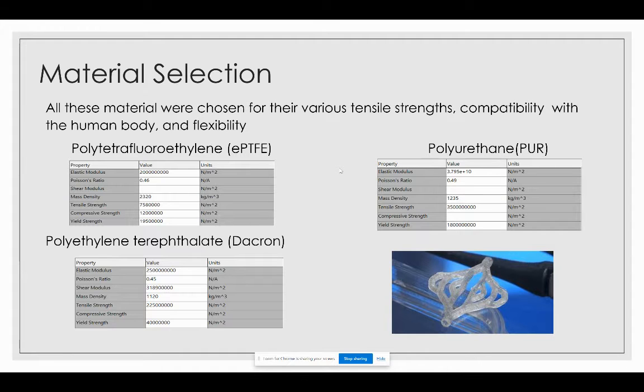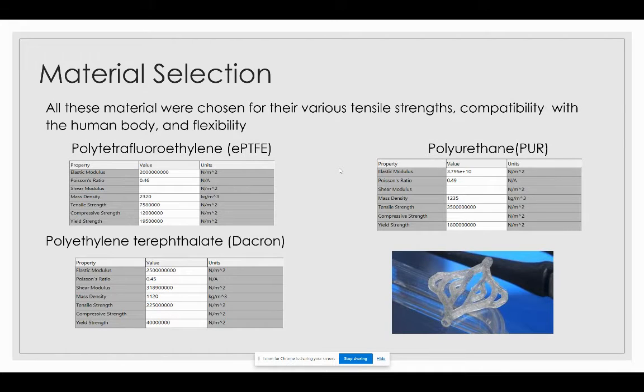For material selection, all materials chosen are biocompatible with the human body. They were chosen for their tensile strengths, their flexibility — which is important given the artery's location — and their ability to not deteriorate under the human body's pH. The first material is polytetrafluoroethylene, referred to as PTFE. The key material properties entered into SolidWorks include elastic modulus, mass density, tensile strength, and yield strength.